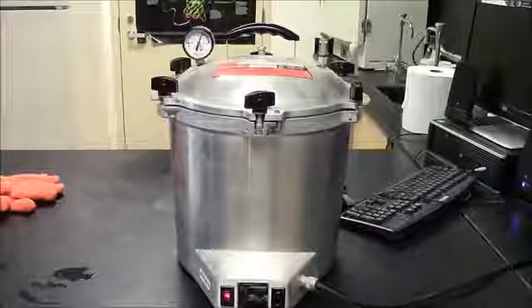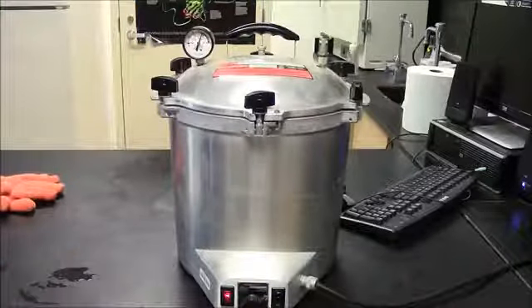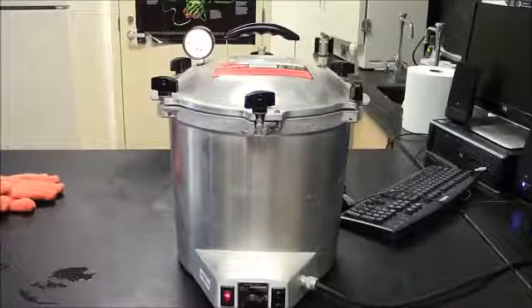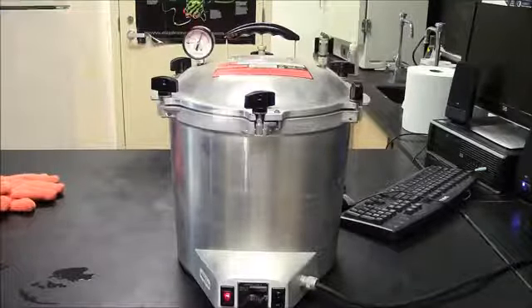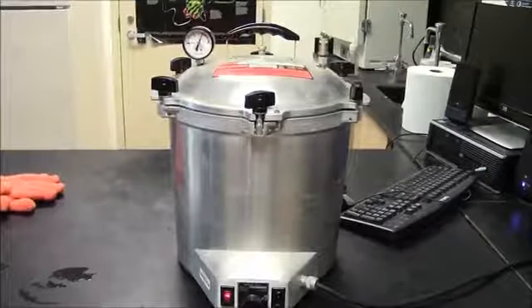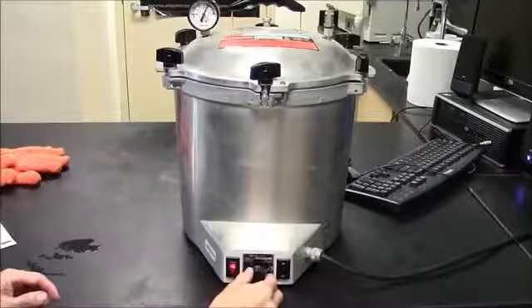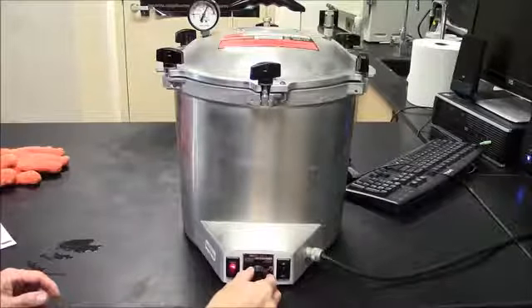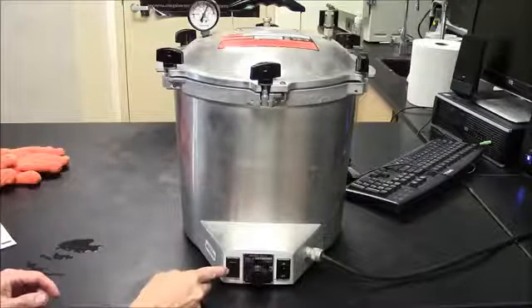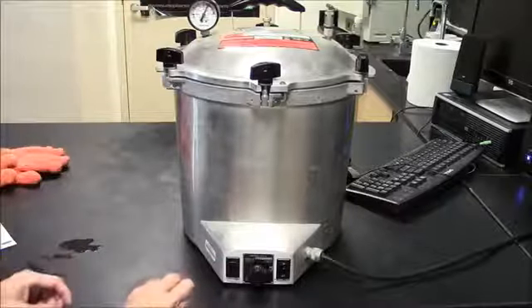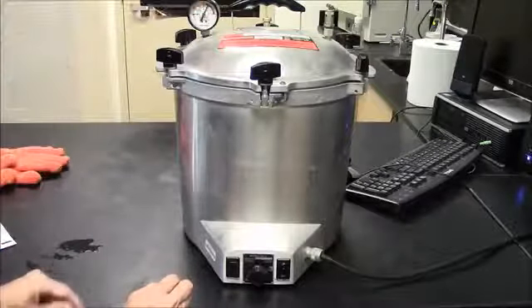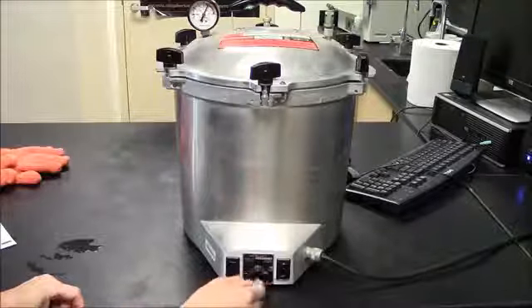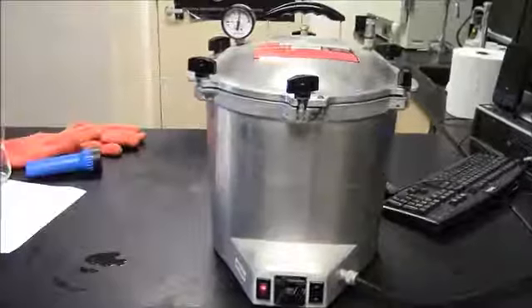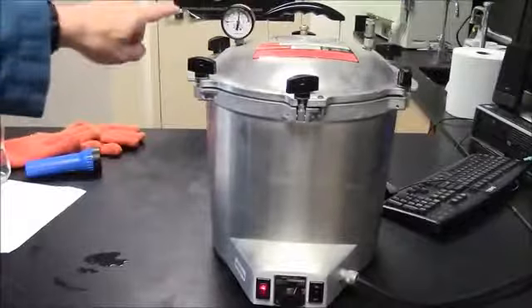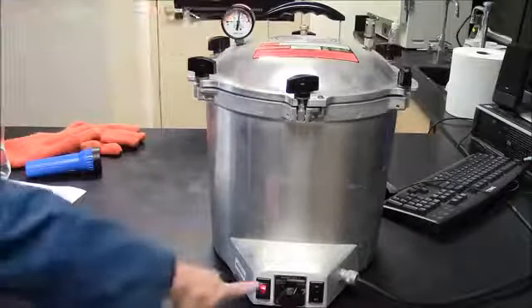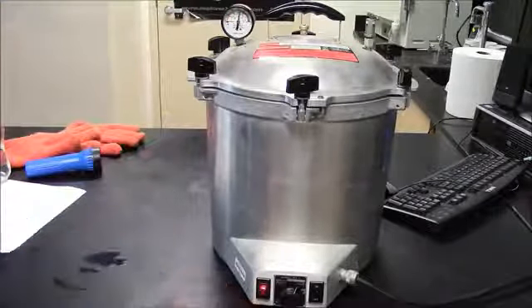You can see that the light down here is still on, so now I need to make sure we don't go into the red zone up here. Don't want to get to the red. So I'm just making a wee adjustment here. Light went off, so I'm no longer heating, but I have to make sure that as this pressure starts to drop, I don't let it drop too far. So I'll turn this knob back up maybe. So here it's dropped just below the green zone, so I turned it up again, get this red light on.